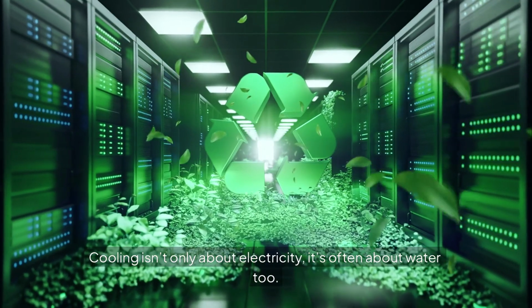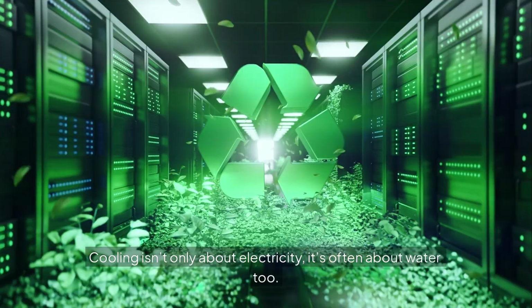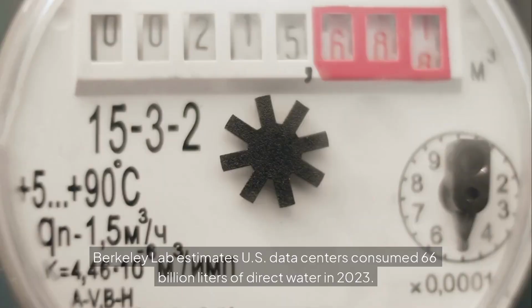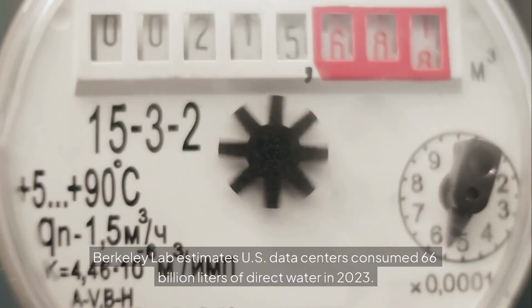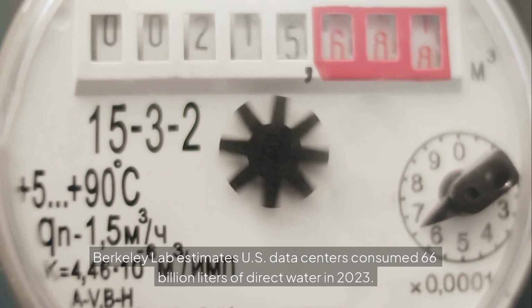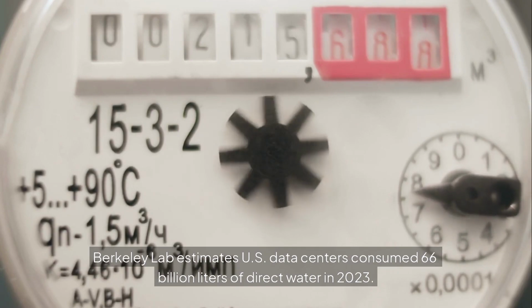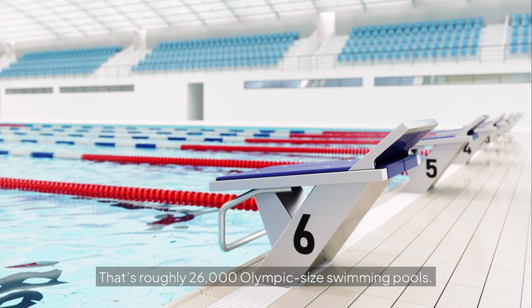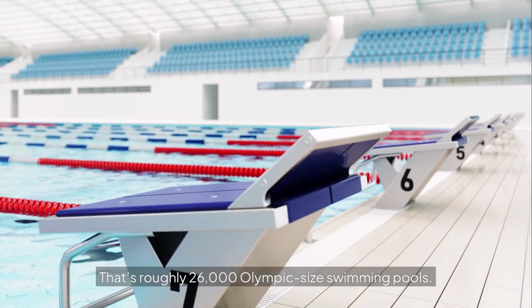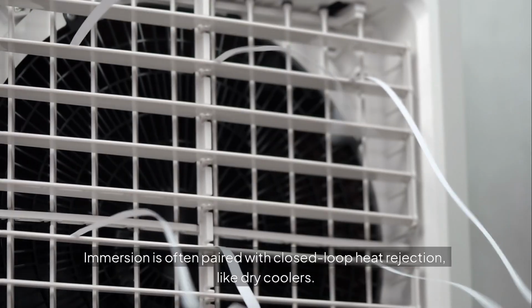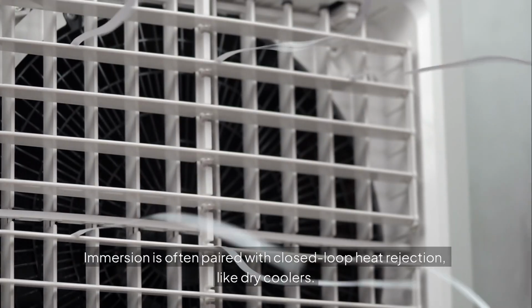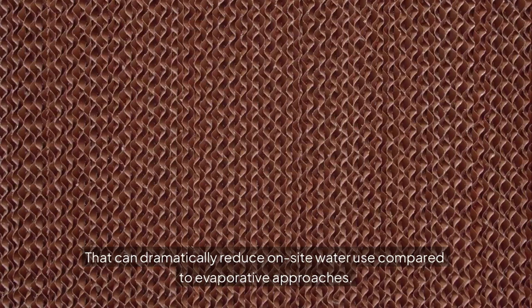Second, immersion cooling can reduce water use in the right setups. Cooling isn't only about electricity, it's often about water too. Berkeley Lab estimates US data centers consumed 66 billion litres of direct water in 2023. That's roughly 26,000 Olympic-sized swimming pools. Immersion is often paired with closed-loop heat rejection, like dry coolers. That can dramatically reduce on-site water use compared to evaporative approaches.